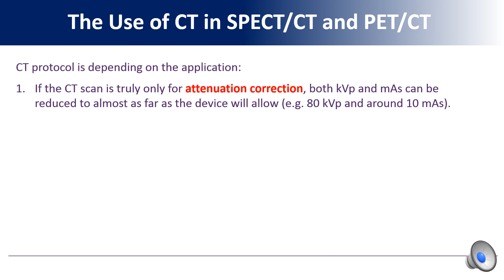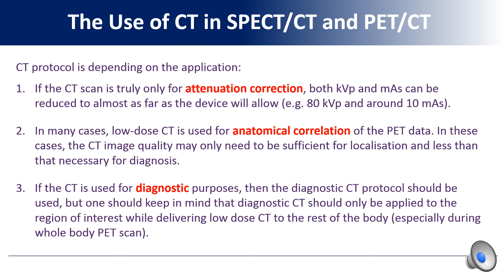In many cases, low-dose CT is used for anatomical correlation of the PET data. In these cases, the CT image quality may only need to be sufficient for localization and less than that necessary for diagnosis. If the CT is used for diagnostic purposes, then the diagnostic CT protocol should be used. But one should keep in mind that diagnostic CT should only apply to the region of interest while delivering low-dose CT to the rest of the body, especially during whole-body PET-CT scan.